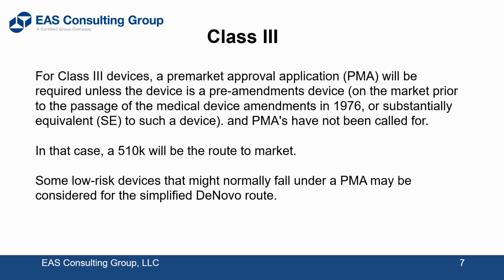So it kind of expands the definition of substantially equivalent to allow for a little bit of improvement, not just proving your product is a copycat of something already out in the marketplace, but proving it basically poses the same risks as something that is out in the marketplace, but may have some slight improvements upon it without getting to the point where you're into a PMA.